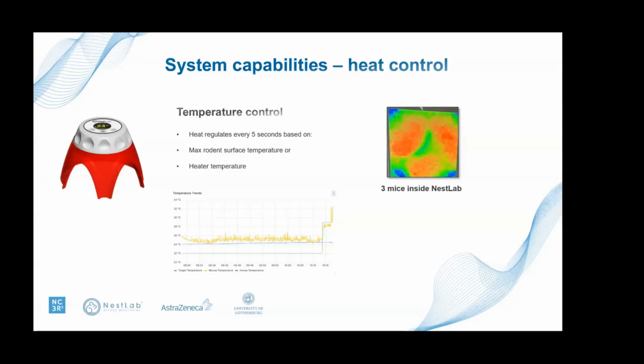So heat control is relevant. Those heaters that I've seen don't have control, and I think you need control to make sure that it's safe. So what you see on the right here is a thermal imaging camera from NestLab, which shows 3 mice inside NestLab. And the color indicates how warm each mouse is. And what we then do is that we regulate the temperature based on either the heater itself or the maximum temperature of the rodent. And we found that we can actually quite accurately get a good surface temperature.